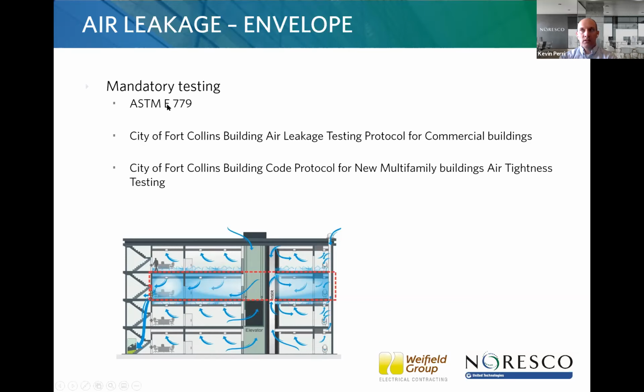I will point out that the ASTM standard passing rate, if you recall, for Denver was 0.40 CFM per square foot of envelope. If you look at the commercial building protocol for Fort Collins, that says passing is 0.25. If you look at the multifamily testing protocol, that says passing is 0.30. So even though you have options to pick from in Fort Collins, you have different passing requirements based on the protocol you're doing. Talk about confusing. That's why we're going through all the different AHJs' amendments right now, but they give you more ability and flexibility in your testing.